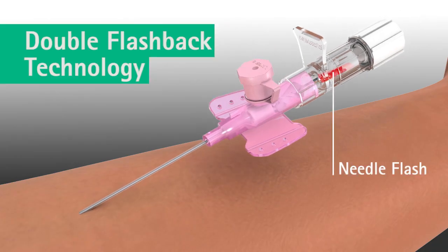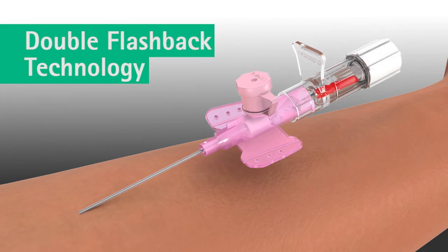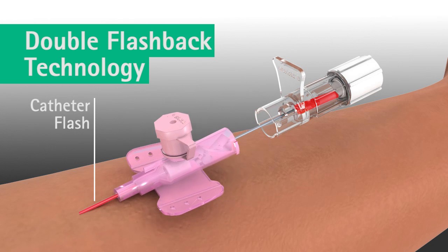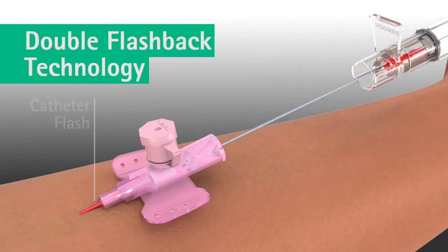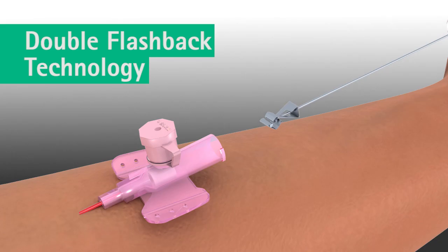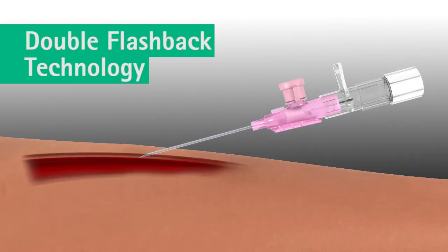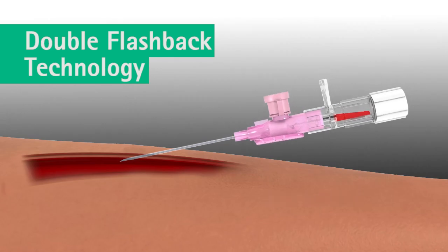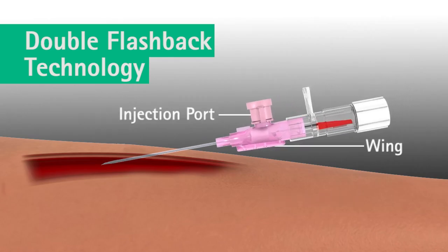Vasofix Safety's double flashback technology improves first stick success through quick visualisation of both the needle flash and the catheter flash. Here's how the double flashback technology delivers this benefit. Upon insertion, the first flashback of blood — needle flash — is visible in the clear flashback chamber confirming the needle tip is in the vein. Using the injection port on the catheter hub or using a wing, the catheter is advanced forward off the needle into the vein.